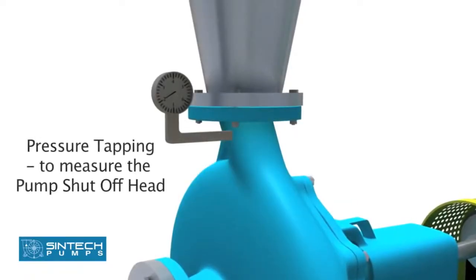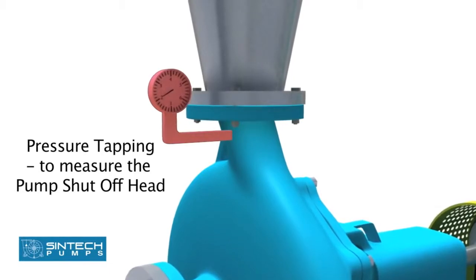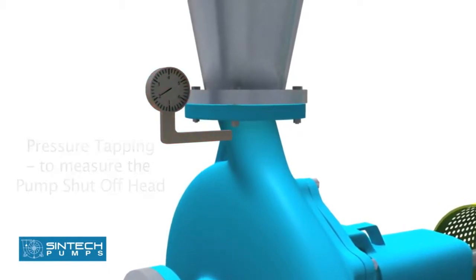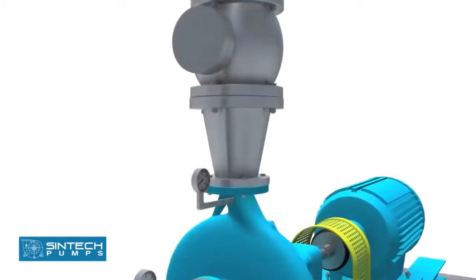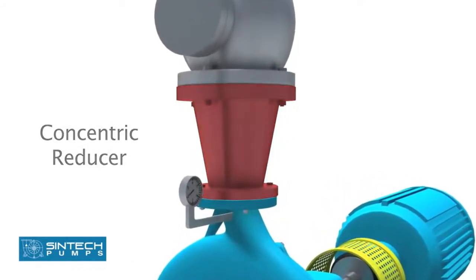There should be a pressure tapping as close to the pump outlet and before the isolation valve as possible to measure the pump shutoff head. Concentric reducers are installed in the discharge pipe to minimize friction losses.